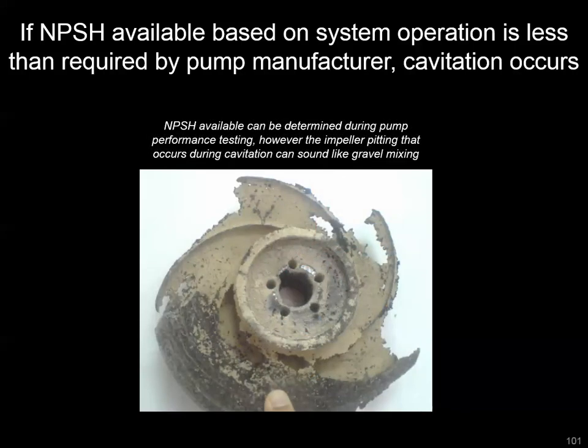Here's an impeller that has had cavitation pretty much eat away at the tips of the impeller blades. You can often tell by a distinctive almost popcorn sound at the pump. This is one factor that goes into designing our pumps, and one reason why an oversized pump that is not throttled or balanced can run out its curve — as we'll show on the pump curve — and cause cavitation that ruins the impeller and affects pump performance.